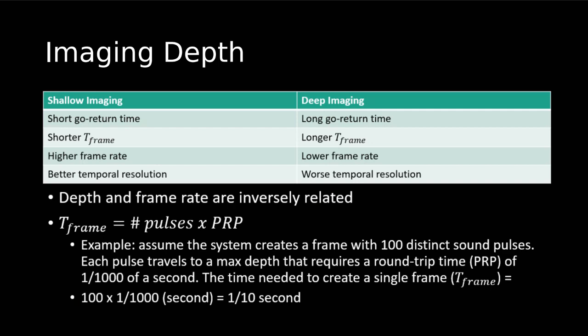With shallow imaging, we don't need as much depth, so we have a shorter go-return time — 13 microseconds per centimeter. With shallow imaging, we have a shorter T-frame, a higher frame rate, and better temporal resolution. With deeper imaging, we need more depth — the sound wave travels further and takes double the time to return. This gives a longer T-frame, lower frame rate, and worse temporal resolution.